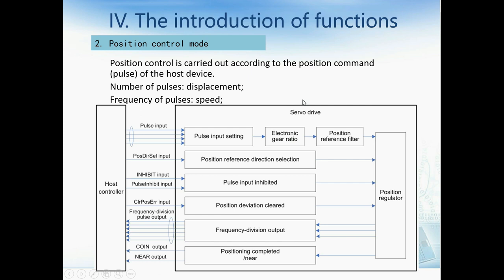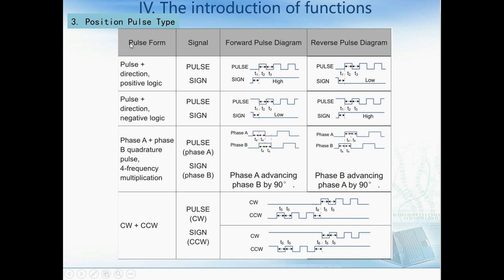There are several pulse types. The most often used is pulse plus direction — one signal for output pulse and another signal for controlling direction. The second type is AB phase signal. AB phase signal has no separate signal for controlling direction, because it defines the direction according to the phase differential between phase A and phase B. When phase A is advanced ahead of phase B by 90 degrees, it means the direction is positive; otherwise it means negative.